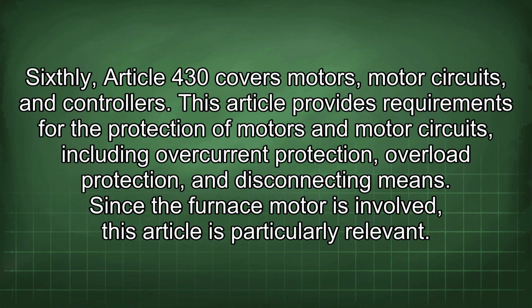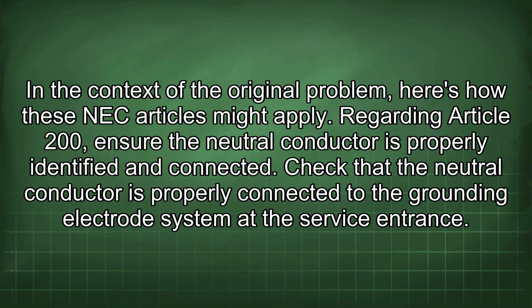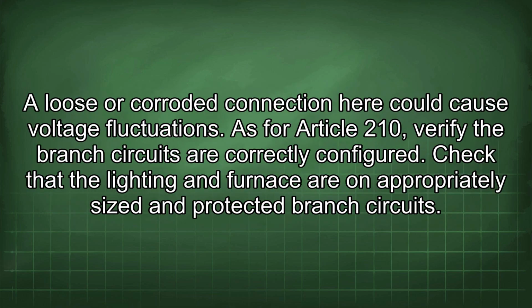Sixthly, Article 430 covers motors, motor circuits, and controllers. This article provides requirements for the protection of motors and motor circuits, including overcurrent protection, overload protection, and disconnecting means. Since the furnace motor is involved, this article is particularly relevant. In the context of the original problem, here's how these NEC articles might apply. Regarding Article 200, ensure the neutral conductor is properly identified and connected. Check that the neutral conductor is properly connected to the grounding electrode system at the service entrance. A loose or corroded connection here could cause voltage fluctuations.